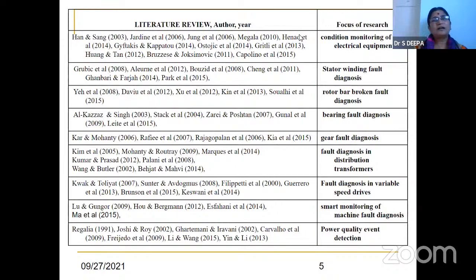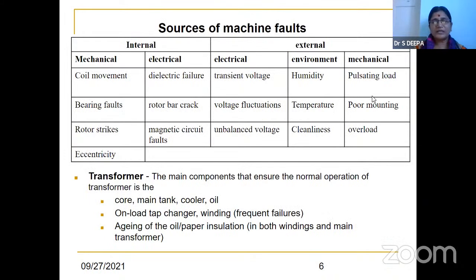Here we have the literature. What are the papers that discuss this? The focus is on research in condition monitoring of electrical equipment. Electrical equipment means, nowadays, special machines are also coming in, and then you have induction motors, transformers, everything is electrical equipment. Stator winding; our power grid is also a network, so there also you can have different equipment embedded in it. Stator winding fault diagnosis: first we consider the motor, so stator, rotor, bearing fault, gear fault. Then fault diagnosis in distribution transformers, fault diagnosis in variable speed drives, smart monitoring of machine health diagnosis, power quality event detection. These are the topics that I will be touching upon.